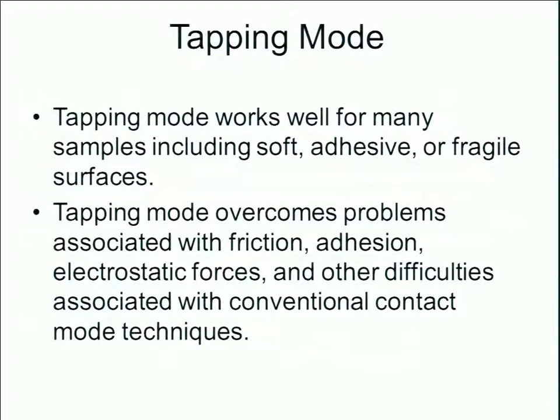Tapping mode works extremely well for many different samples, including soft, adhesive, or fragile surfaces. The reason is that tapping mode can overcome common problems arising from sample and probe interactions, such as friction, adhesion, electrostatic forces, and other difficulties that arise with general contact mode techniques.